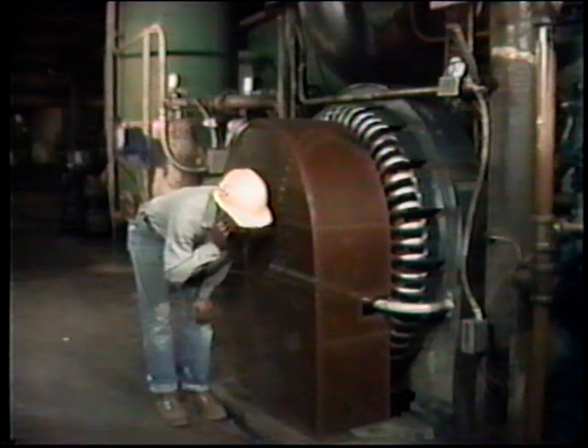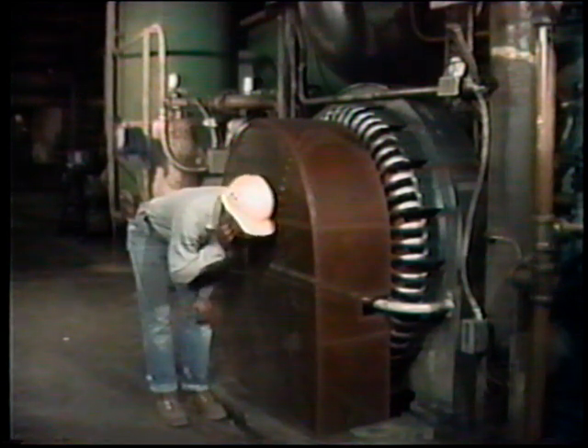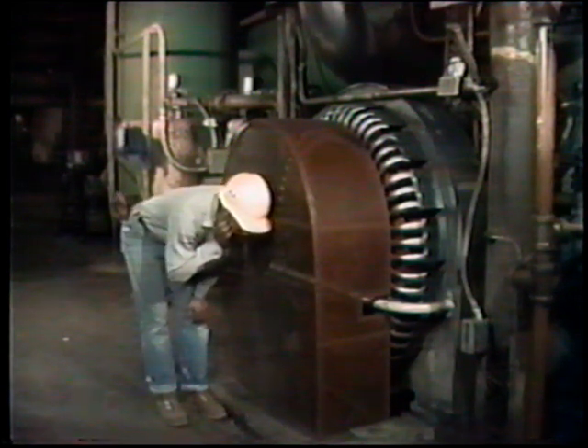Before inspecting a synchronous motor that is operating, follow all your plant's safety procedures concerning operating electrical equipment. Be sure to remove any wristwatches, rings, or other accessories that might conduct electricity. Button any open shirt cuffs and make sure your clothing isn't loose enough to become entangled in moving machinery. Then listen carefully to the motor's sound. It should sound smooth and steady. An unsteady sound or an increase in noise may indicate that a problem exists.